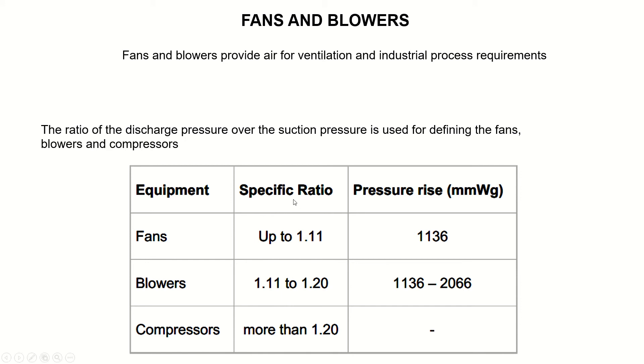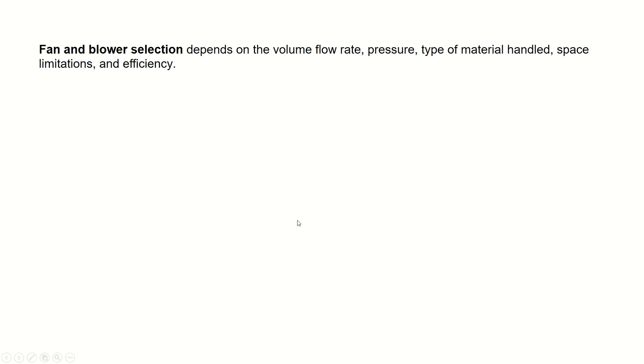Fans are typically used for low pressure applications. Blowers are used for medium range pressure applications, with a pressure ratio between 1.11 to 1.20. Compressors are used for high pressure applications where the pressure ratio is more than 1.20.